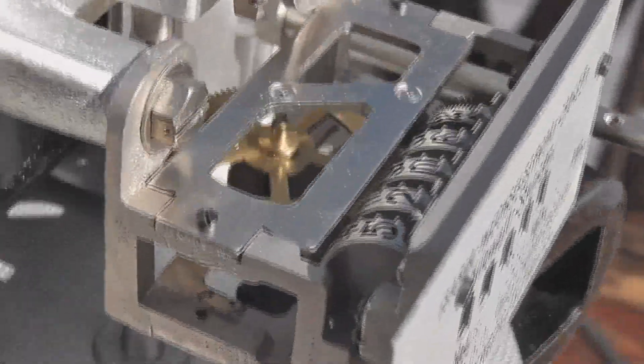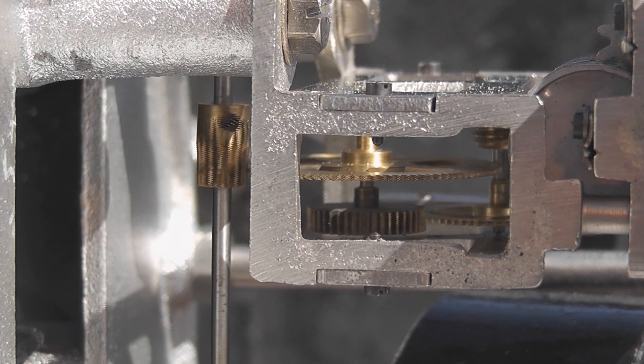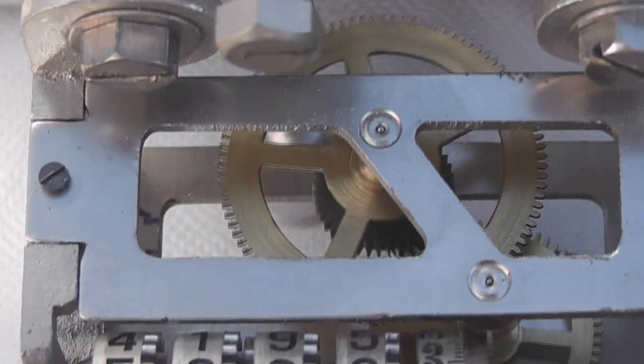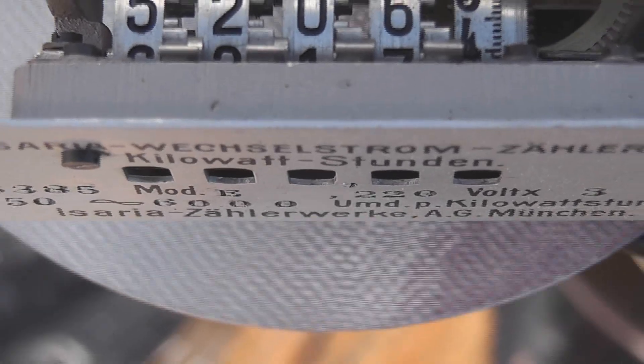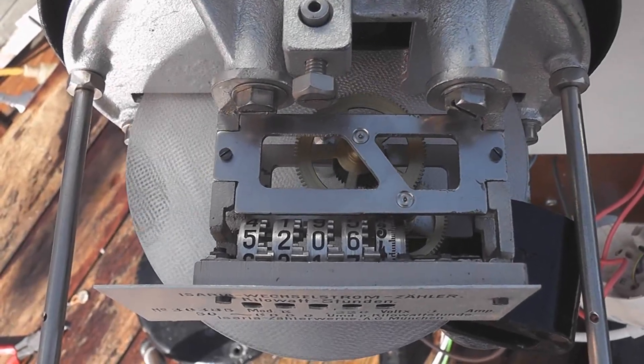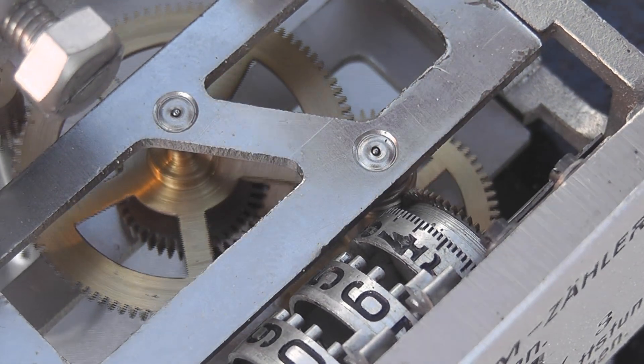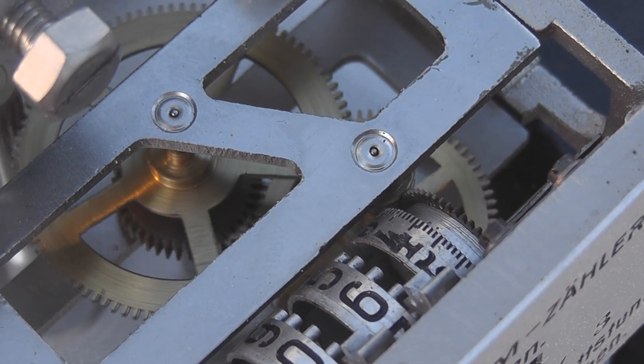Let's do a quick overview drive. Top view of the meter. Here we have some fine engineering — gear drive into a gear train into the register. Here we have the top view of the meter train. The counter measures in 10 watt-hour increments. Here we've got the disc. We've got a pinion wheel here on the spindle, an intermediate gear, and then another gear which drives the register by means of a worm drive.